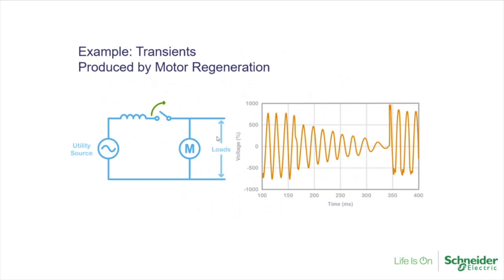And then this is an example of transients produced by a motor regeneration. You can see that it was running, came down, and tried to come back on. And you can see the transients, or peaks, at the end of the sinusoidal wave shape on the bottom.